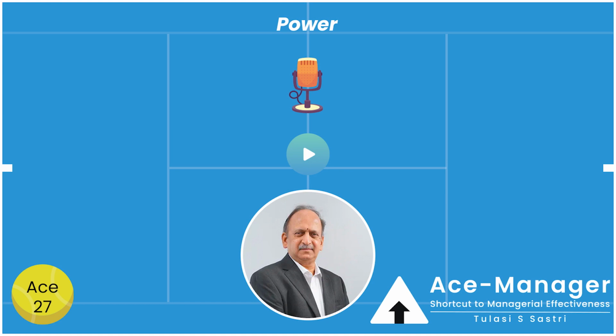I realized that there is merit in replacing these 3 old gensets with another 1000 kVA set. Based on my recommendation, the old 3 generator sets of 250 kVA each were replaced by a new generator of 1000 kVA. It meant significant savings in power generation, and the payback period for the investment in the new set was less than 3 months.